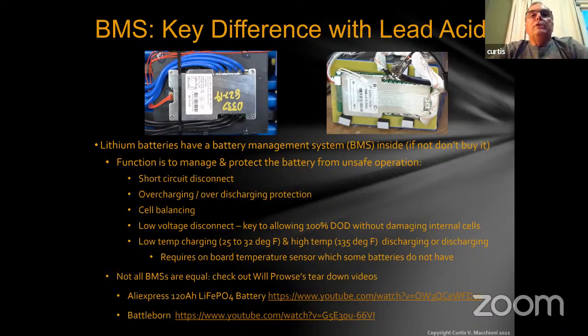So make sure no cell gets overcharged compared to its partners, and no cell gets more discharged than its partners. And it will have a low voltage disconnect. Once the voltage goes to a certain level, which is the minimum safe voltage to not damage the lithium cell, the battery management system will cut off the output abruptly. That's the key to allowing 100% depth of discharge without damaging the internal cells.